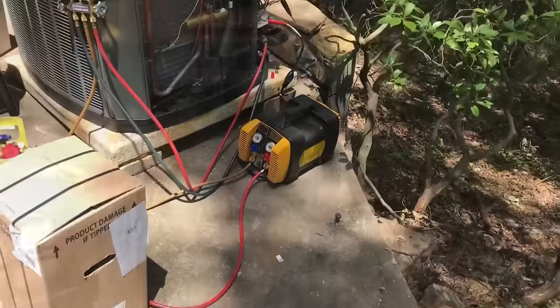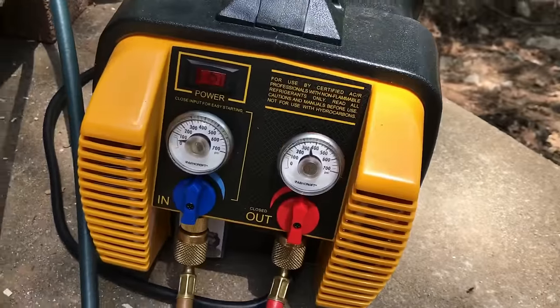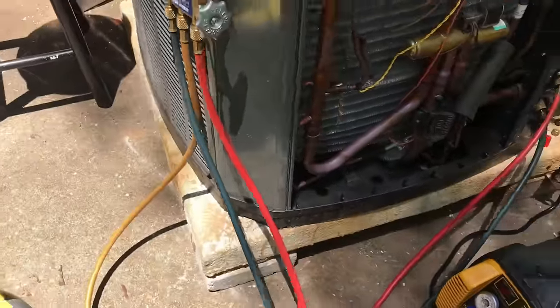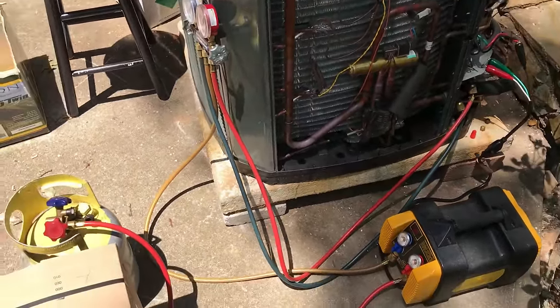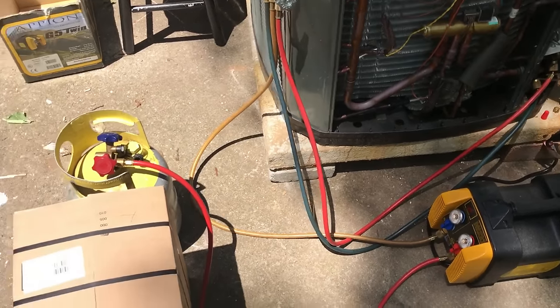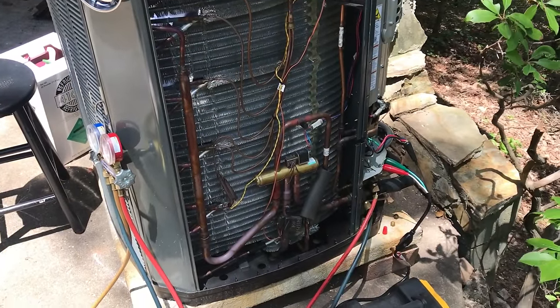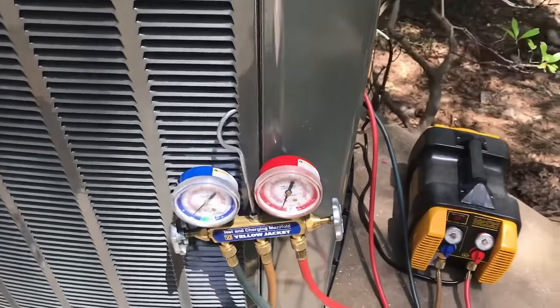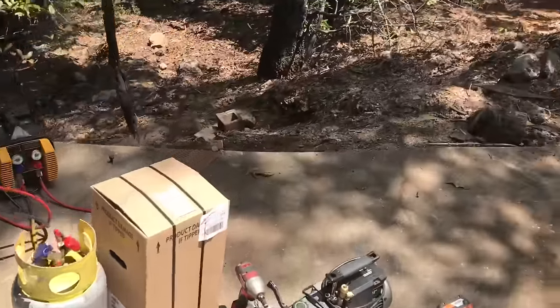We're using the Appion recovery machine with analog gauges hooked to it. This compressor is dead short to ground, so I'm not a hundred percent positive what the condition of the oil and refrigerant in the system is. So I'm recovering to a cheap set of gauges and keeping our good ones over here until we decide what we're going to have to do.